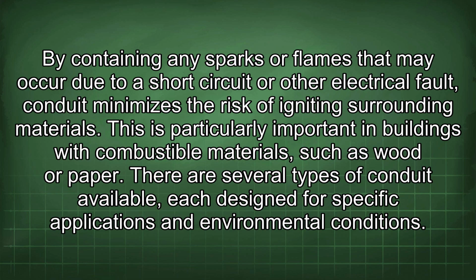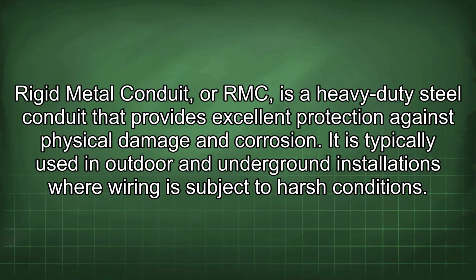There are several types of conduit available, each designed for specific applications and environmental conditions. Rigid metal conduit, or RMC, is a heavy-duty steel conduit that provides excellent protection against physical damage and corrosion. It is typically used in outdoor and underground installations where wiring is subject to harsh conditions.